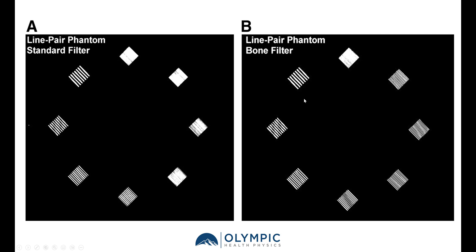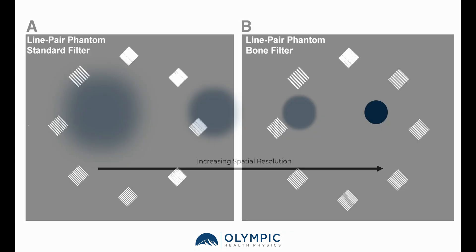Whereas when we apply the bone filter, we can see not only the seven, but we can also see the eight, nine, and ten line pair patterns. So you can see how applying a different filter can change the resolution of the system.